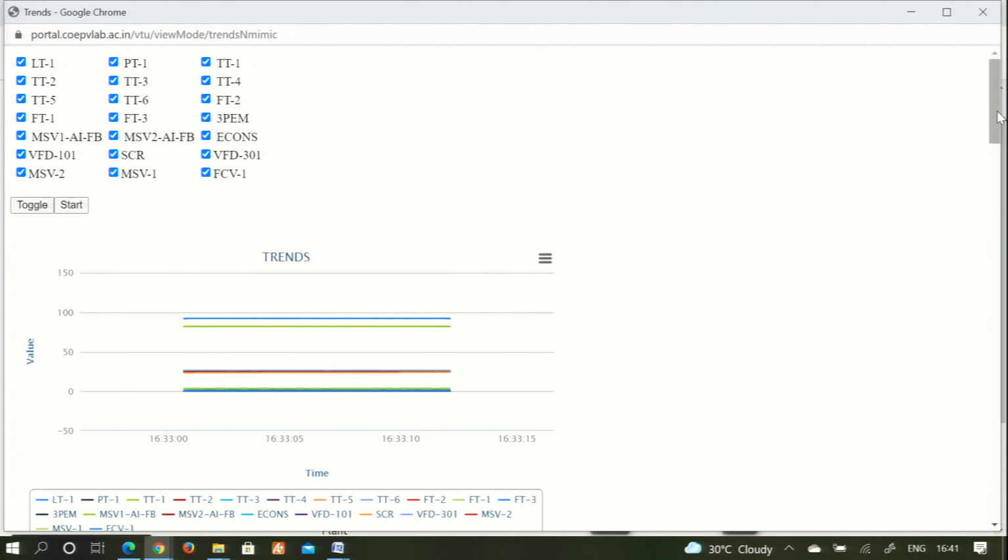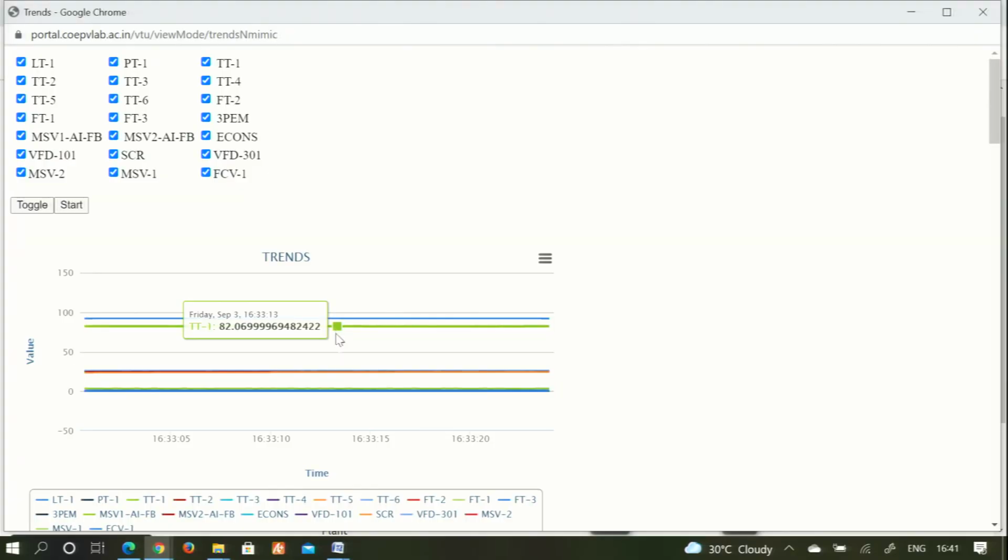So, if I am a passive user of this system, I can see what is happening here, and then I can say, oh my God, temperature has gone above 80, still he has not taken any action, and still the SCR is at 24%. So, that is the learning actually, where the student who is not operating the plant will keep in mind that the firing angle should have been 0 actually, why 24, what is wrong here.